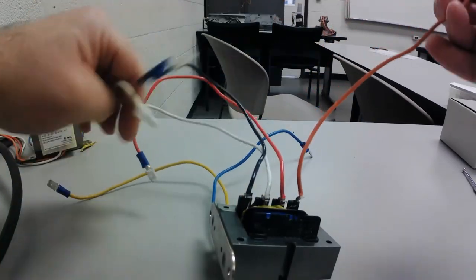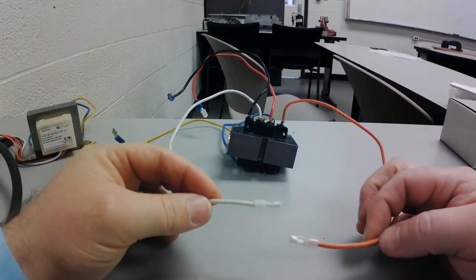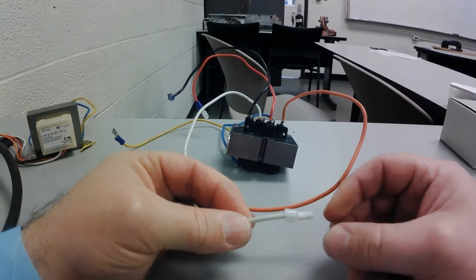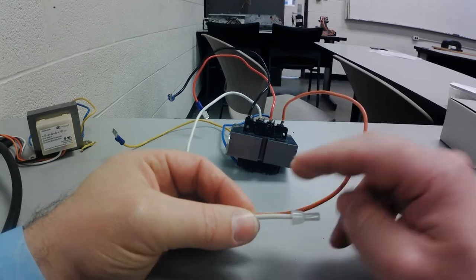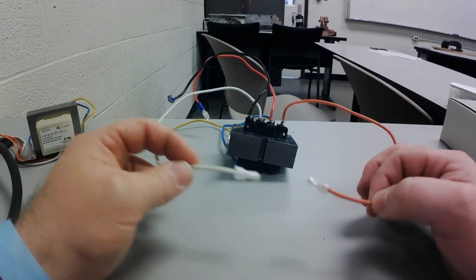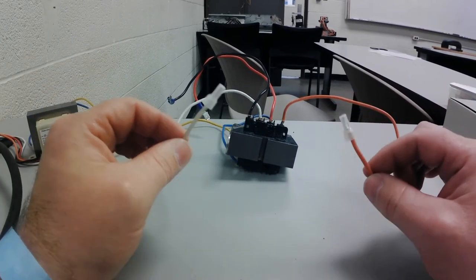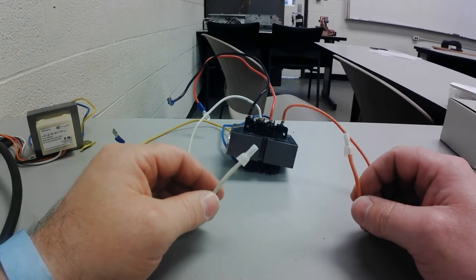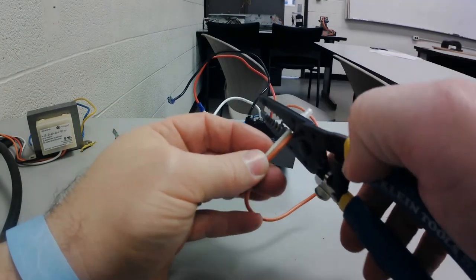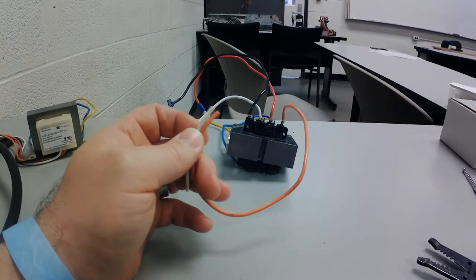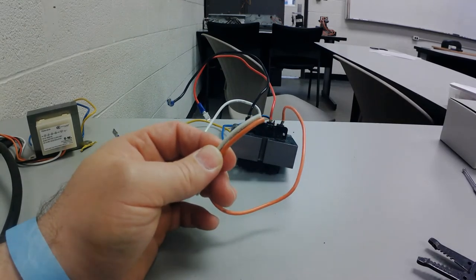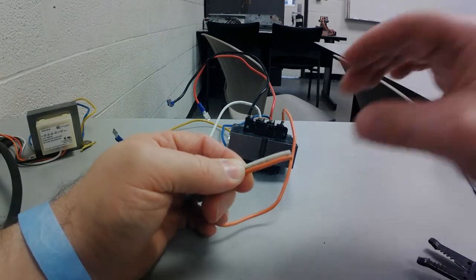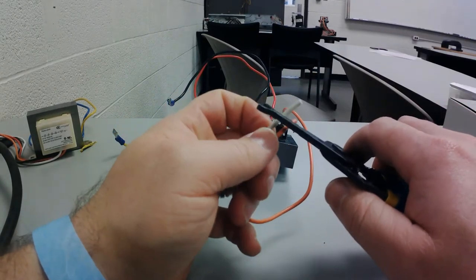So that is the reason that when you get a multi-tap transformer or a multi-speed motor that's a PSC, what you need to do is take the single wire individually and make sure that you put a connection on the end to isolate it so it doesn't touch the aluminum foil lining on the inside of the air handler. It doesn't touch the case to ground it out, because this wire, even though it's not being used, it still has power on it. And some guys I've seen out in the field, they'll take these unused wires, and they'll put one wire nut on both of them. You can't do that because now you're getting into another bad situation, okay?